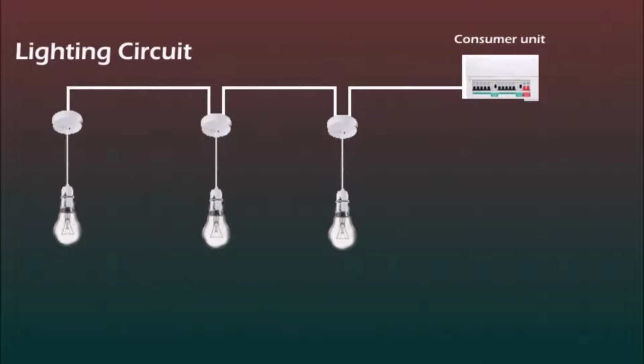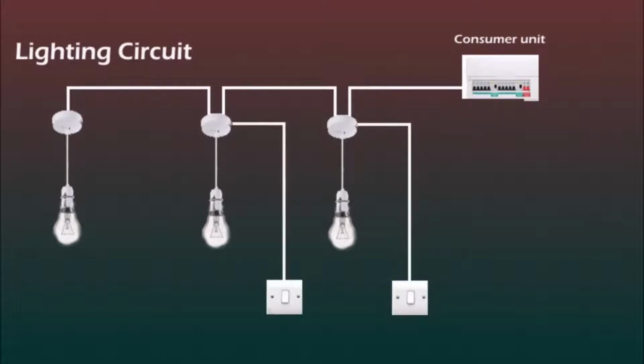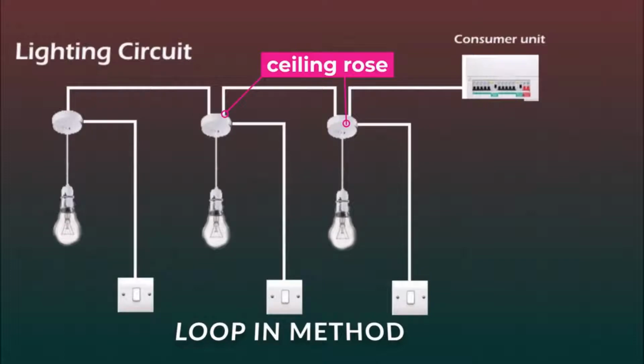There are 3 methods of how you can run the lighting circuit. Unlike the power circuits, the lighting circuits are more complex, as the cable not only goes from light to light, but also need to be split at some point to fit the switch in every lamp location. The first one is called a loop-in method, and you can see it on this picture. Every ceiling rose, the live wire splits to fit the switch.